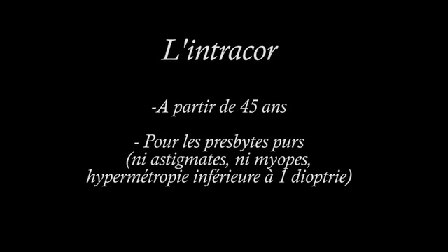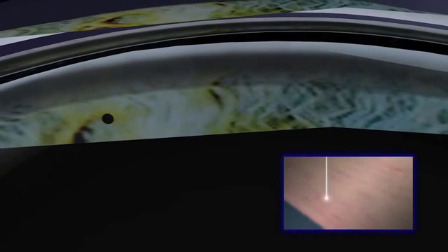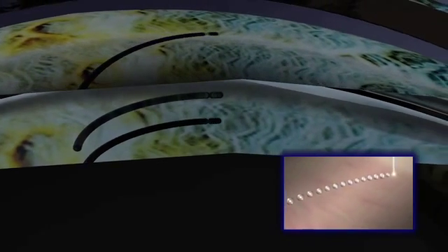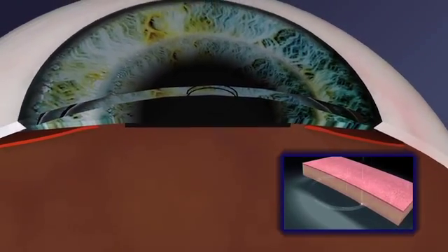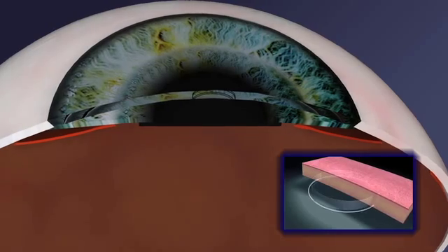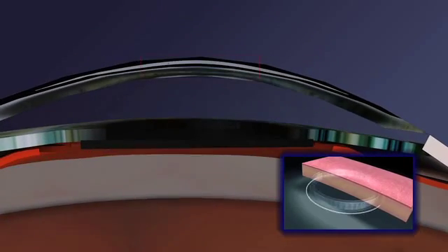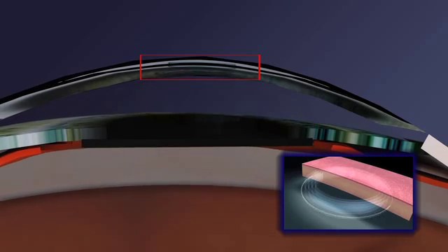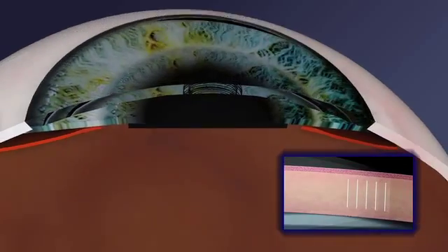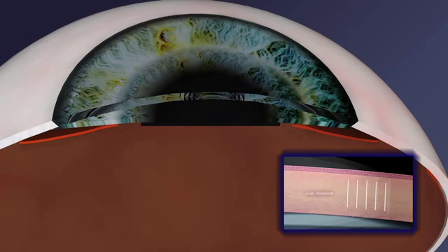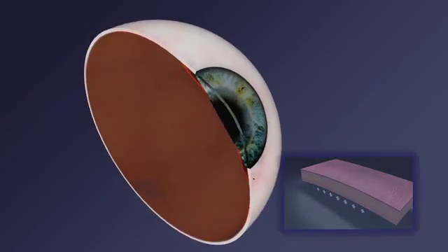IntraCor is a very simple method that uses femtosecond laser to change the shape of the cornea without cutting a flap or ablating tissue. The device cuts a pattern of five concentric rings within the stroma. These rings are placed from 1.8 to 3.6 millimeters in diameter at the center of the cornea. These cuts change the mechanical structure of the cornea and induce a central steepening which affects the dioptric power of the cornea.